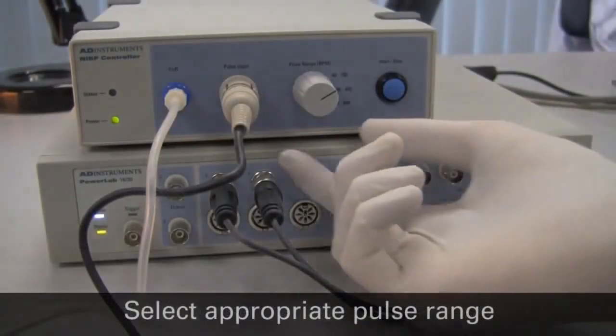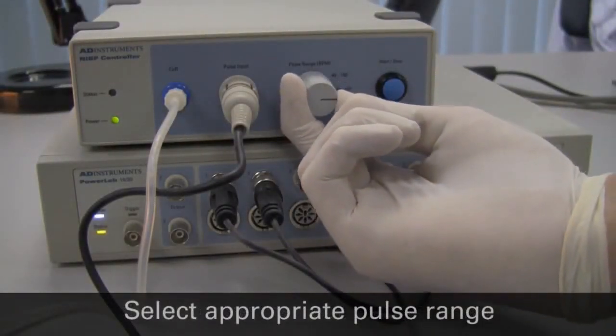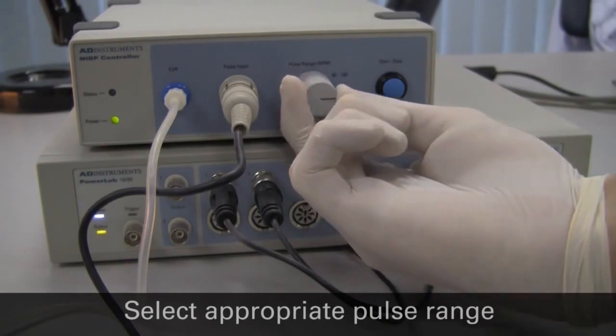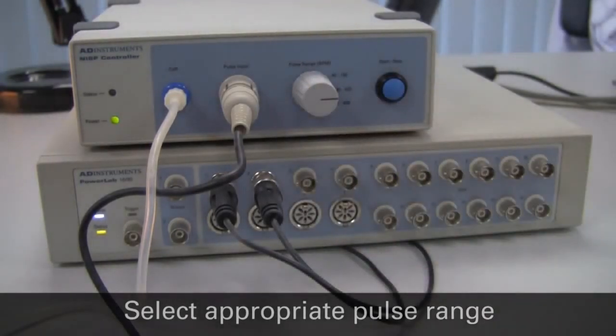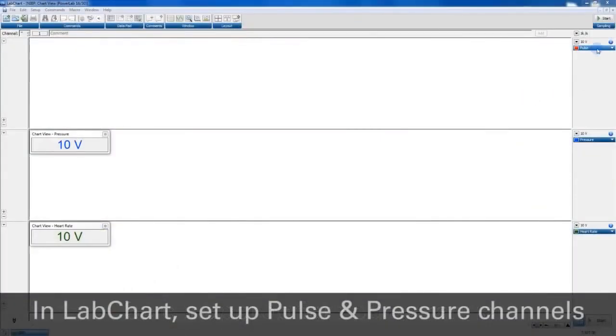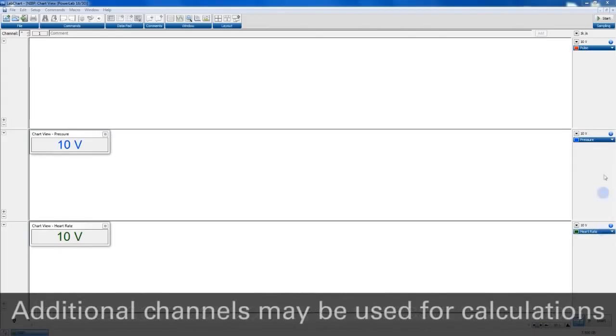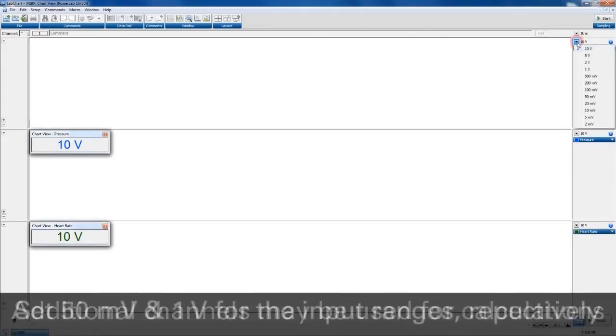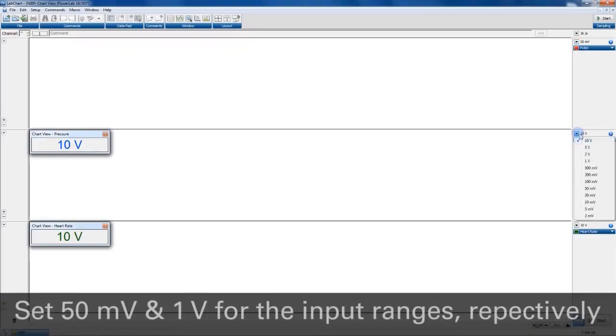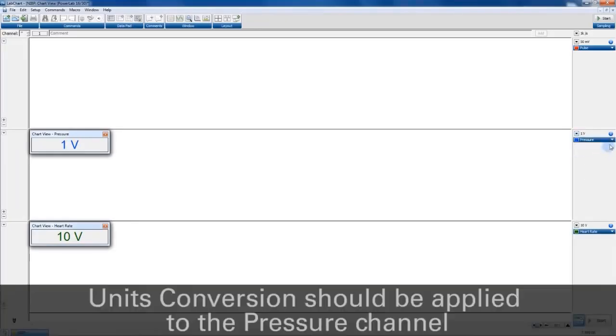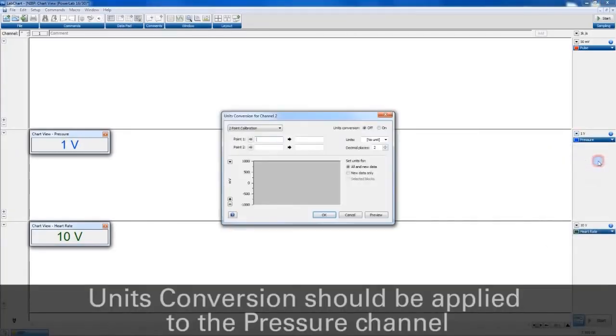Select the appropriate pulse range on the front of the NIBP controller. The maximum cuff inflation pressure can also be selected on the rear panel. In LabChart, set up two channels, one for the pulse signal and the other for pressure. You may also like to use cyclic measurements in the third channel to calculate heart rate from the pulse signal. The pulse channel range should be set to 50 millivolts and the pressure channel range should be set to 1 volt. Units conversion should be applied to give 0 volts equal to 0 millimeters of mercury and 1 volt equal to 300 millimeters of mercury.